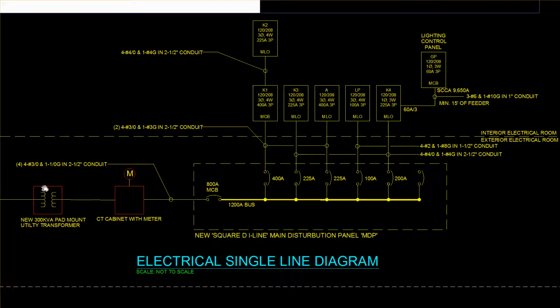And then you'll see some callouts. This piece here is a main distribution panel. You see the main distribution panel, Square D I-Line panel. And the Square D I-Line panel, I happen to know if you get the 1200 amp bus, it will take 400 amp circuit breakers as branches, which is what we wanted in this particular instance. And so each of these is a panel board that's used for power distribution within this restaurant. And then we have a main disconnect, which is required.